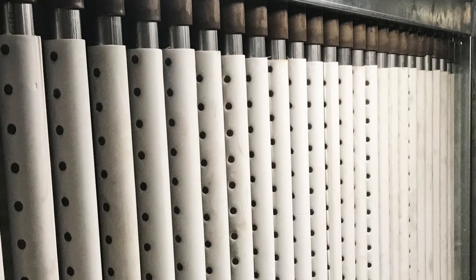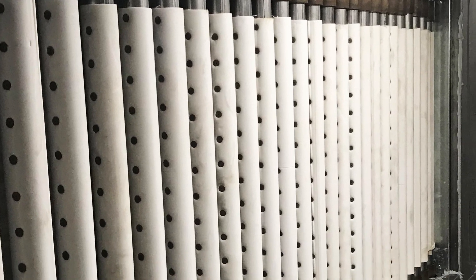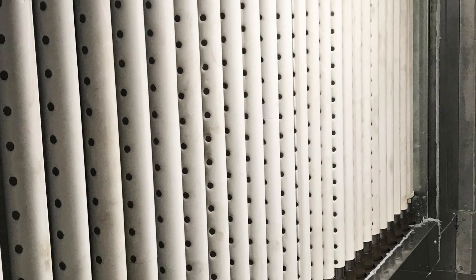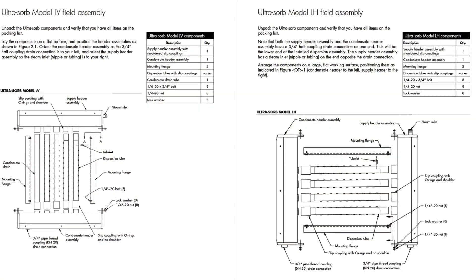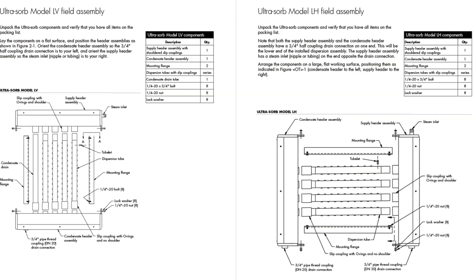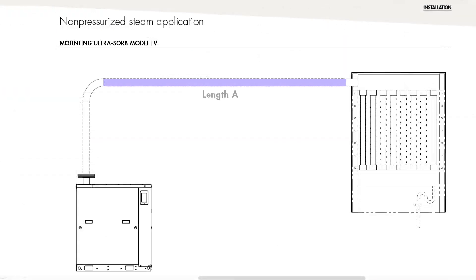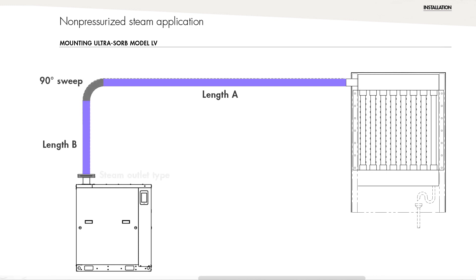Now we'll walk through the components and connection points you'll be working with during installation. Assembling the dispersion panel, refer to the supplied instructions. Measure the actual lineal feet distance from the humidity generator to the dispersion panel. Count the number and type of fittings required to make the installation according to the IOM. Measure space available for a P-trap.